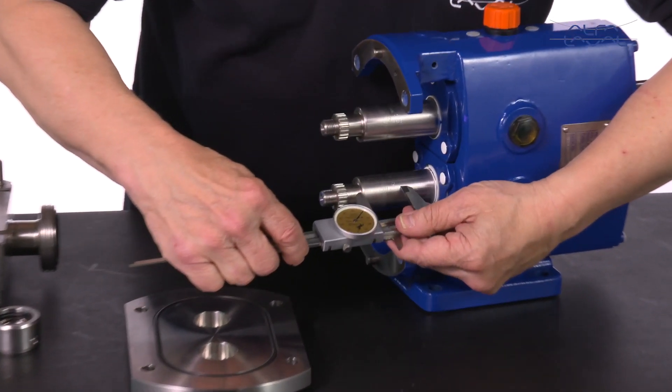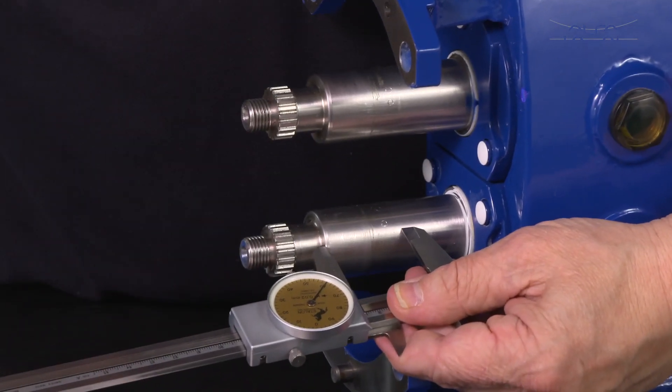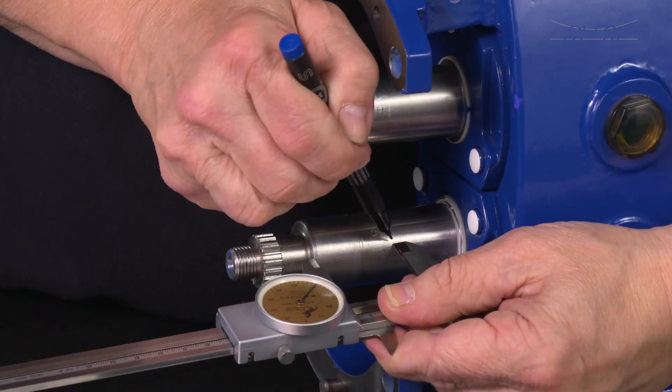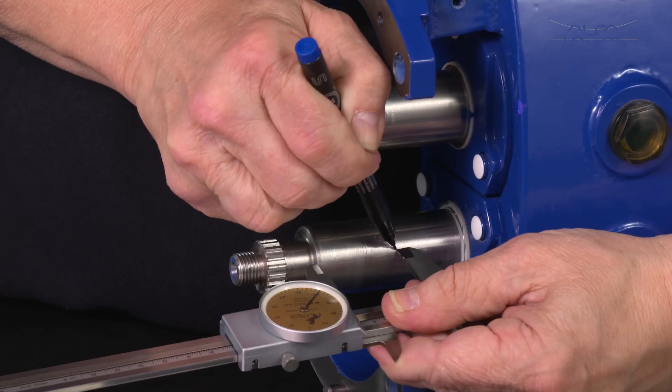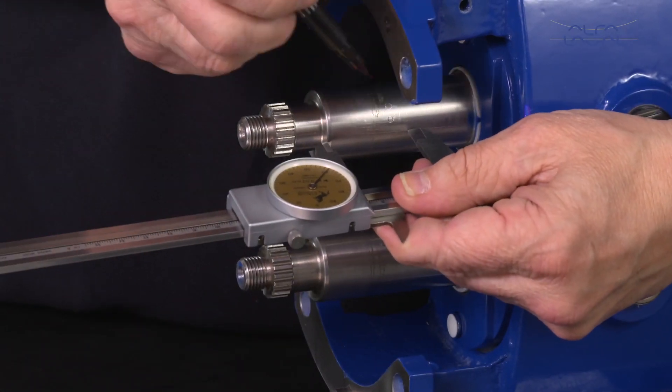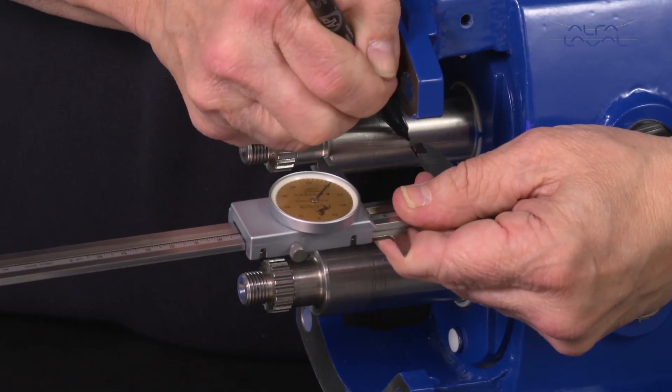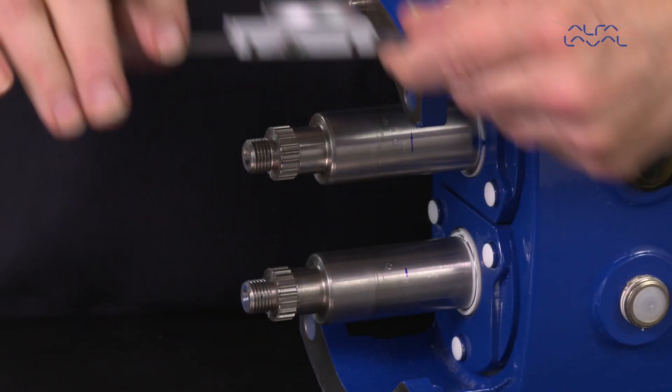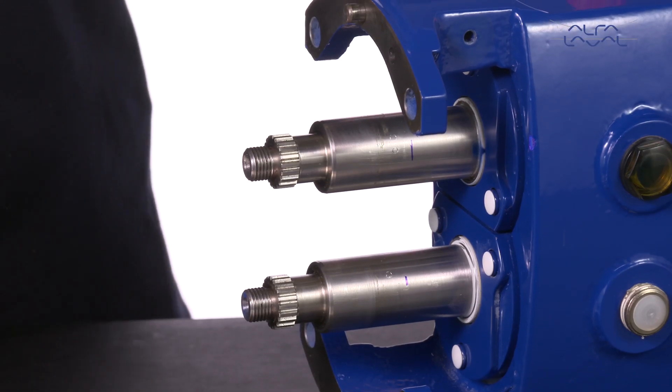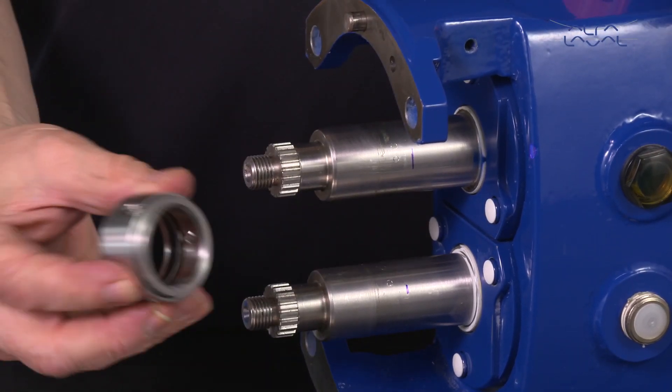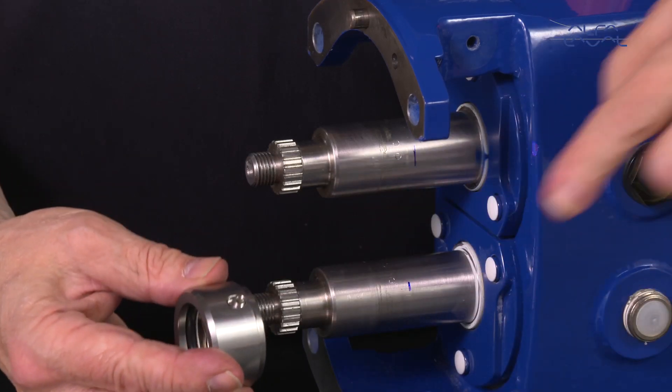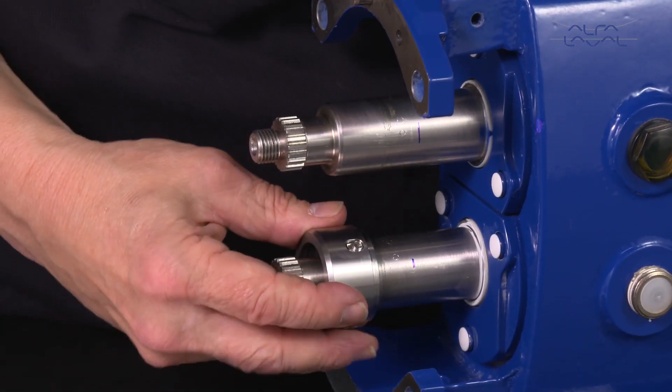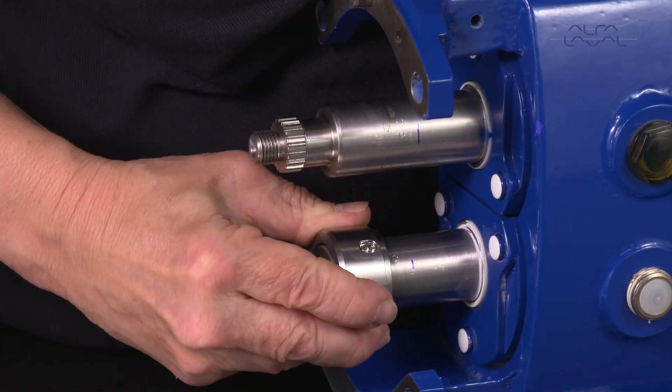Mark the shaft to indicate the seal setting length, shown in the table in the instruction manual. Slide the rotary seal assembly onto the shaft until it is aligned with the mark indicating the seal setting length.